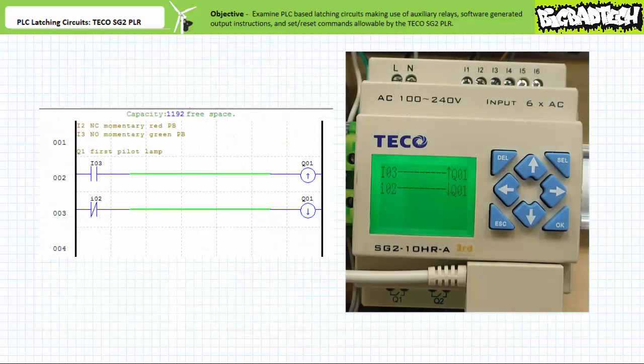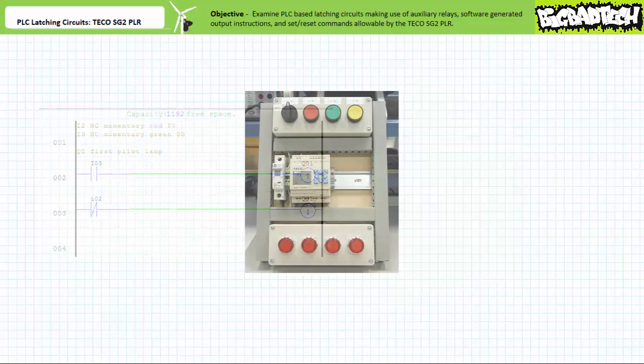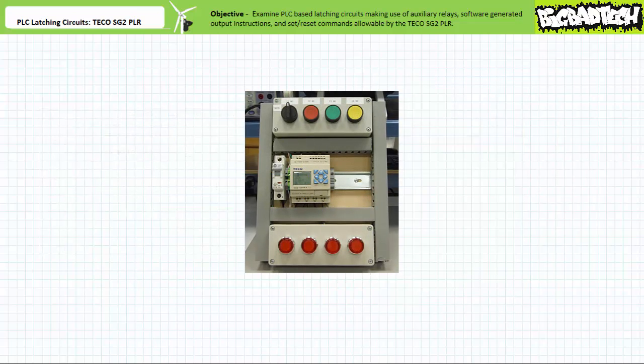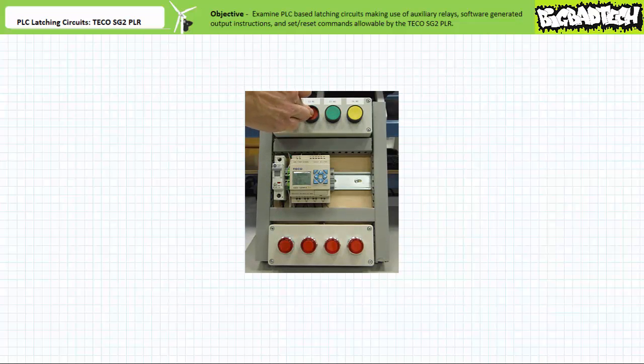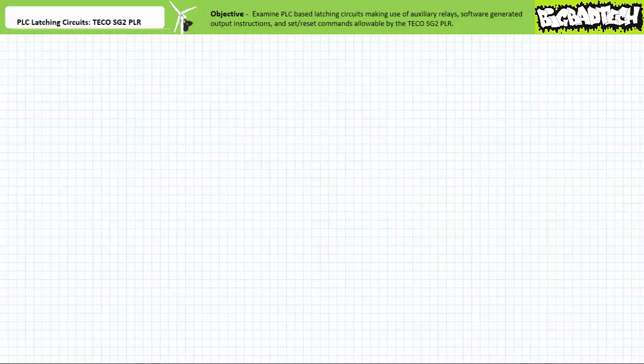When the program is downloaded to a target device, note the subtle formatting differences between the programming software and that employed by the actual device. The set and reset commands are respectively upwards and downwards pointing arrows, and the break command examining input I2 in rung 2 is written in lowercase. Not all manufacturers use this particular shorthand notation. When the system is placed into operation, pressing and releasing the normally open green pushbutton on input 3 turns the first pilot light on and keeps it on. Pressing and releasing the normally closed red pushbutton on input 2 breaks the holding circuit and the first pilot light turns off and stays off. Outwardly, the behavior of this program is identical to the two previous implementations, only the program is ever so slightly easier to read.